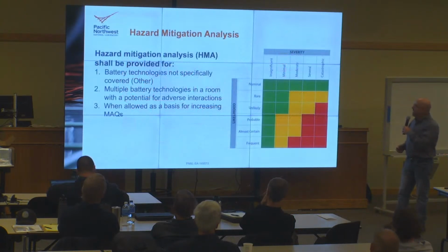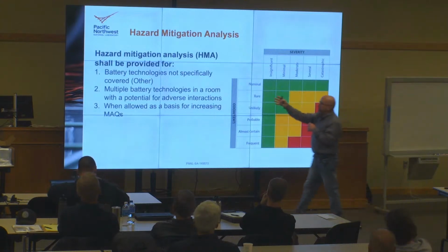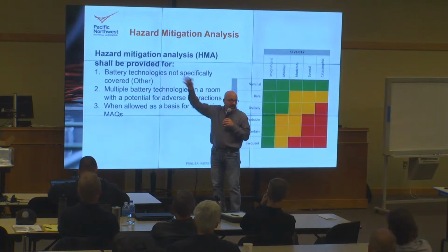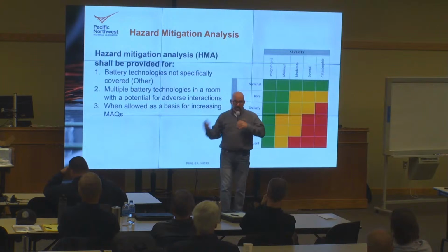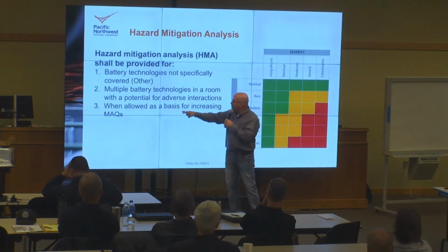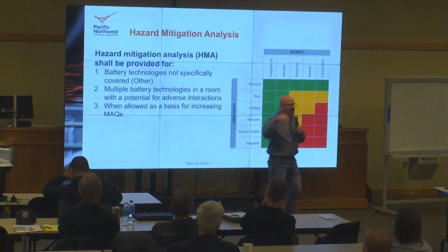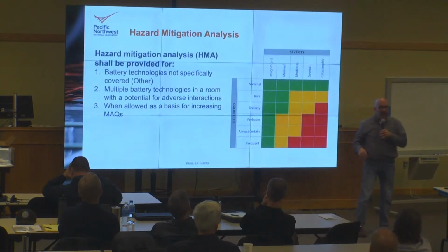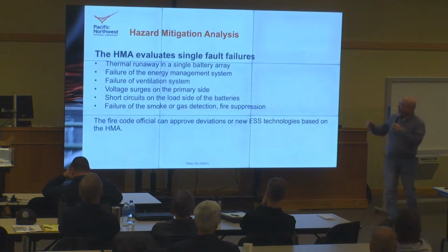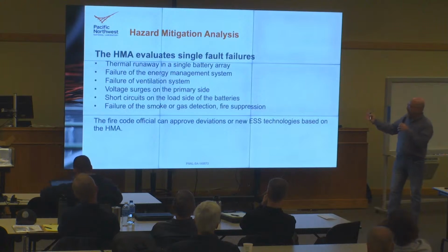So the HMA has 3 criteria that trigger it: some technology not on that table in 855, multiple different technologies in a room with the potential for adverse reactions, or when you want to go over the maximum allowed quantity of 600 kilowatt hours. So then you do an HMA, looking at all the different possible failures, single point failures. What happens when you have thermal runaway in a battery array, the energy management system fails, or a ventilation system fails? It's looking at what all the what-ifs are if this happens.